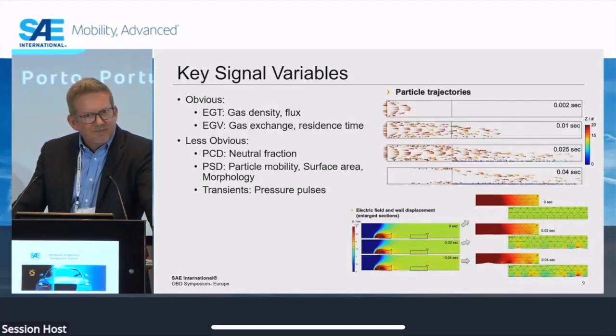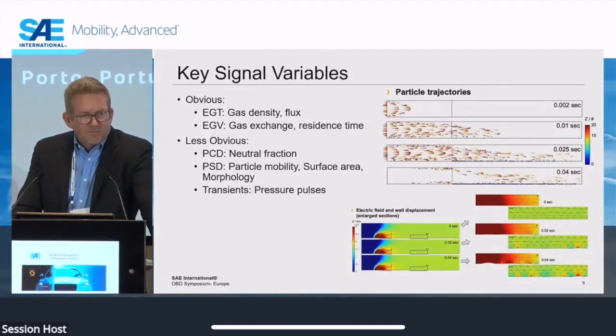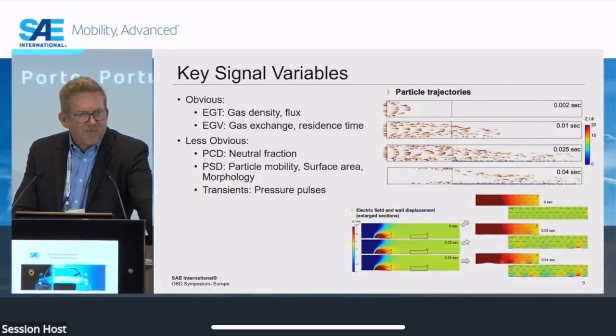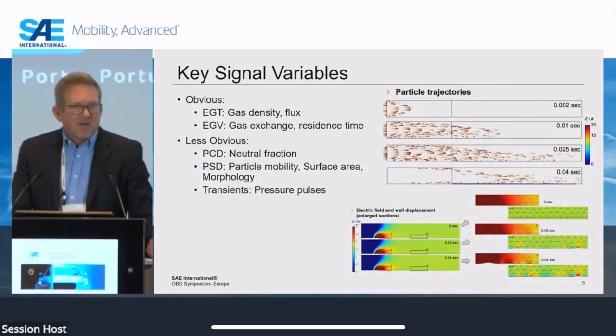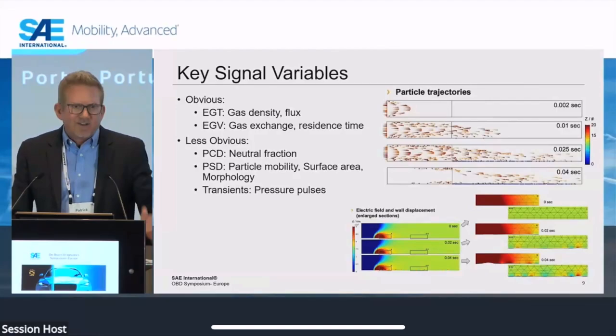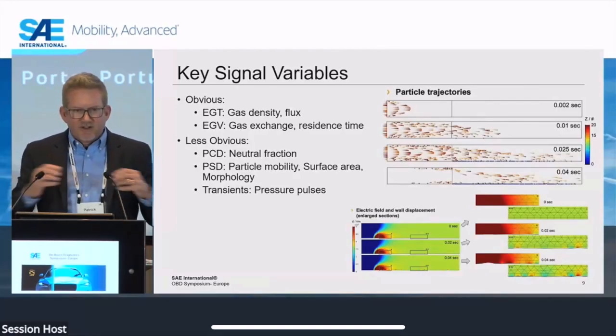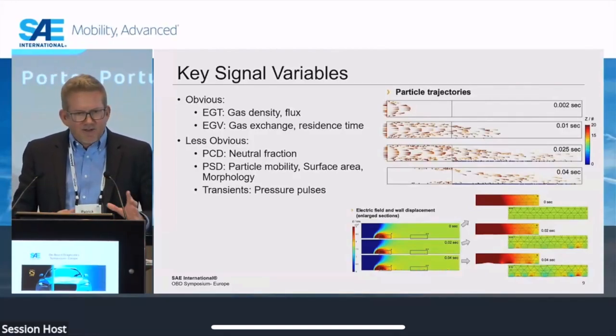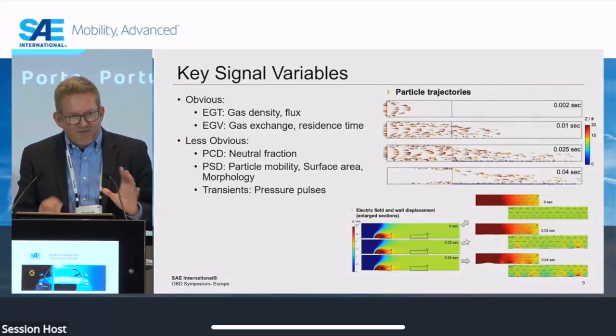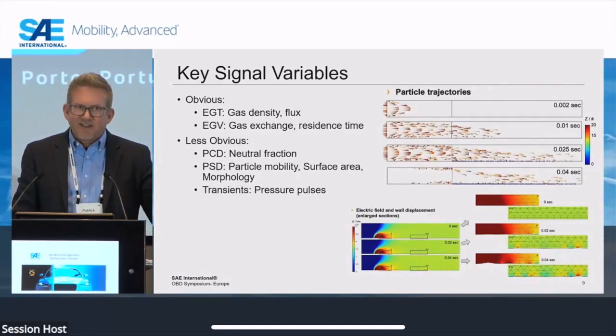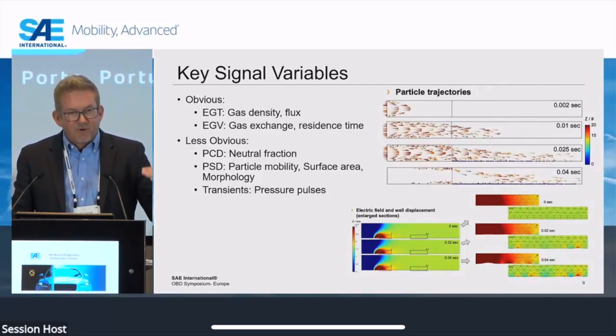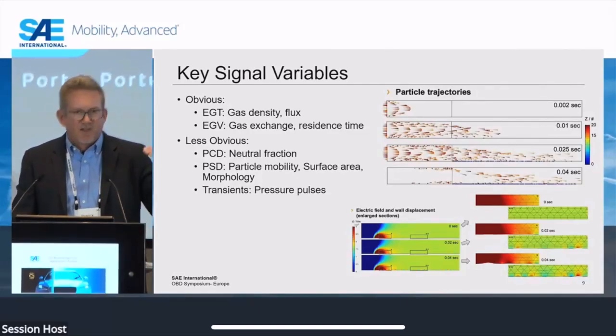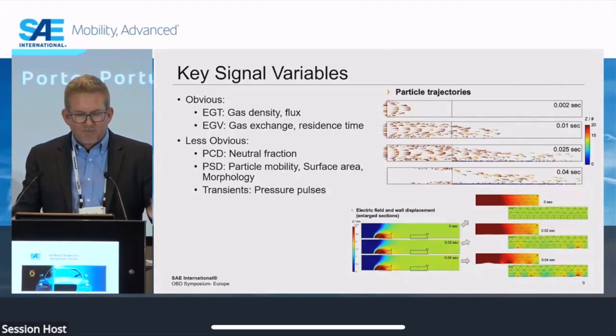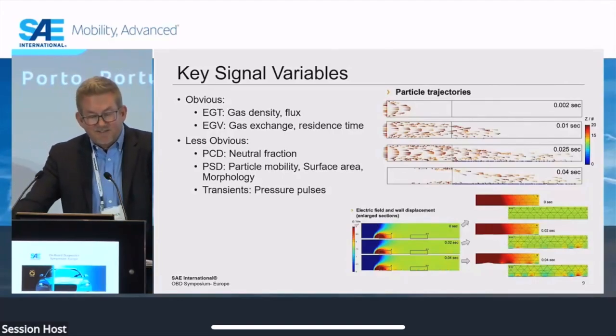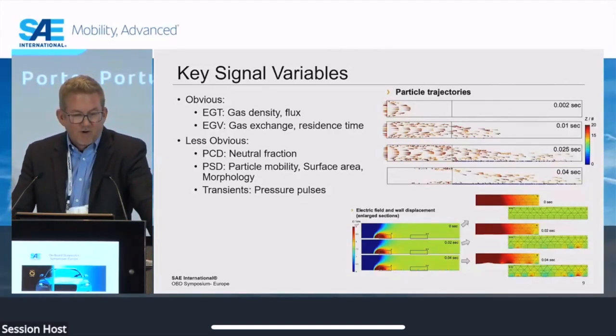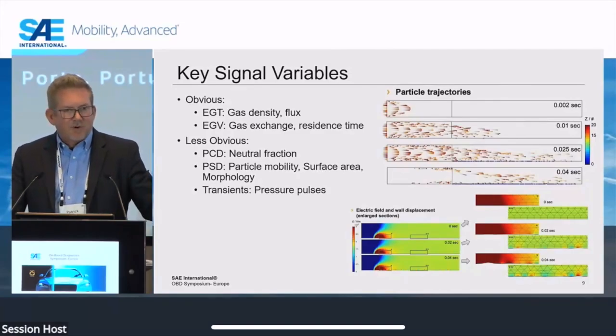The less obvious ones, perhaps, are particle charge distribution. As I mentioned before, the neutral fraction matters. And of course, particle charge distribution is a function of the Boltzmann distribution and combustion temperature. So for an engine family, at any given condition, it's very predictable and very stable. But you still need to understand it, right? If something changes the neutral fraction by a lot, then our sensitivity moves around a little bit. Particle size distribution is the big one that we're going to talk about more. But the particle size, of course, affects particle mobility.